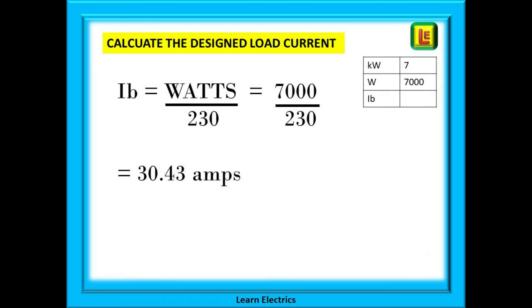First we will calculate IB, the design current. At Learn Electrics we encourage people to make a small chart on the right of the page and fill it in with all the information they have as they come across it. We know that the load is 7 kilowatts, which is the same as 7000 watts. Dividing 7000 by 230 volts gives us 30.43 amps. This is the design current — put that in the chart, as we will need this number later.